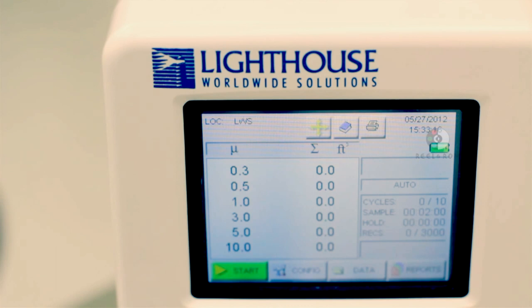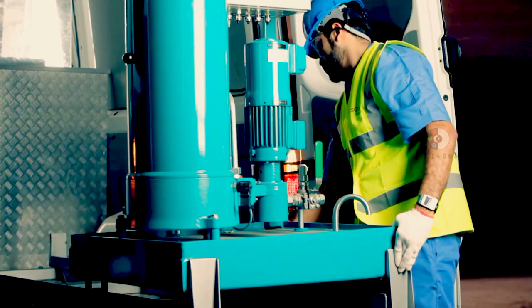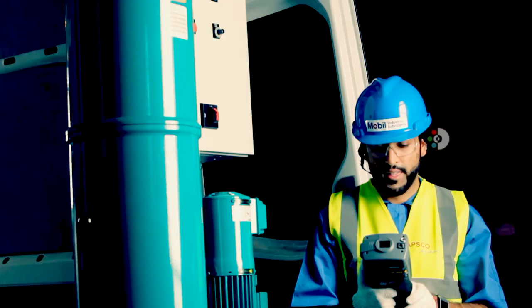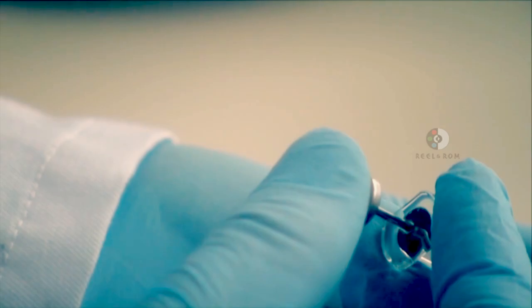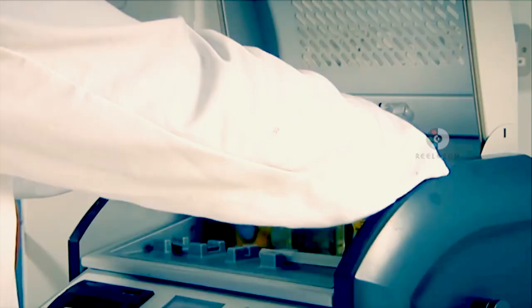Our fourth new tool is called filtration, which is the best method for capturing and retaining fine particles, as well as water and varnish, by installing an offline filter. This filter should operate continuously, circulating the oil volume in the system many times a day, with low pressure and low flow rates. A dense filter medium with a very fine filtration of less than 3 microns can be selected.